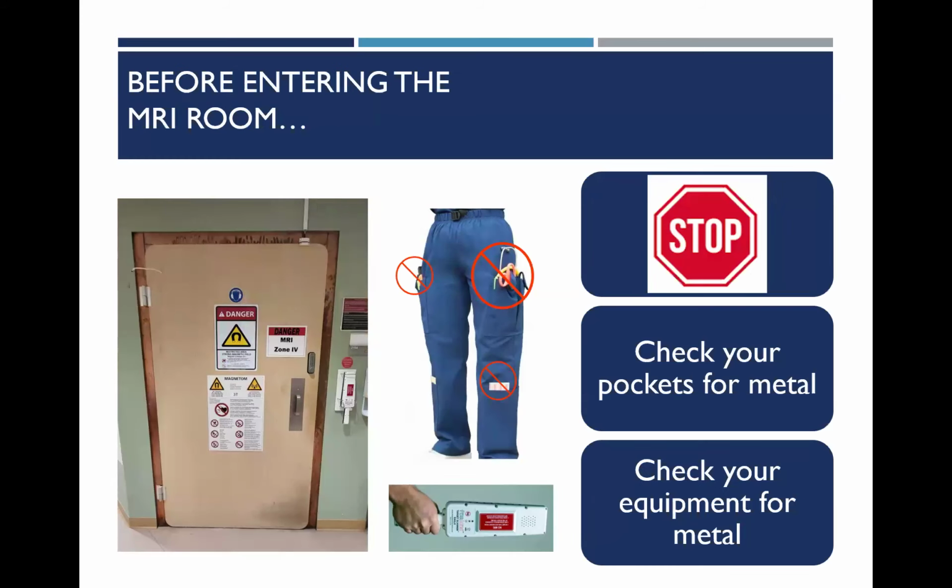So before entering the MR room, stop, check your pockets for metal, and check all equipment for metal using ferrous metal detectors.